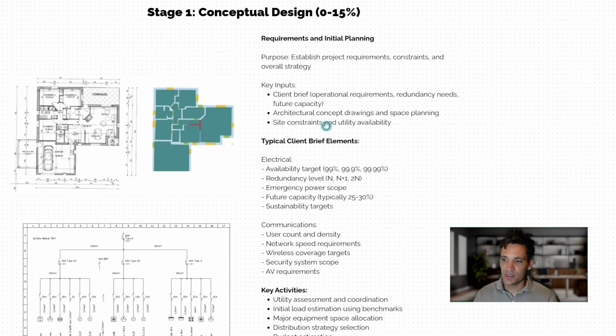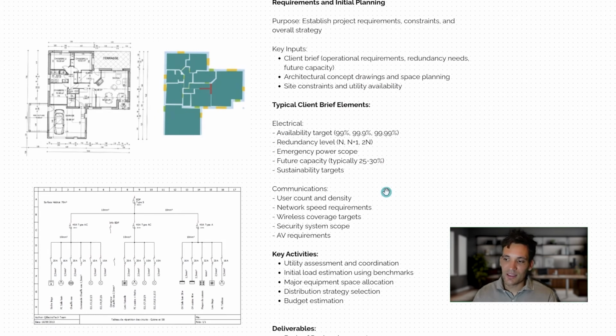So key inputs to this are going to be the client brief, the architectural concept drawings and space planning, site constraints, and the power connection source and utility availabilities. Typically, client briefs will have things like an availability target, whether they want 99% redundancy or 99.99% redundancy, the level of redundancy they expect, the emergency power scope, whether we're required to provide emergency power for anything, future capacity, whether we have to leave 30% spare capacity for future upgrades, and any sustainability targets. Communications might have user counts and densities, expected network speeds, wireless coverage targets, or security system scope.